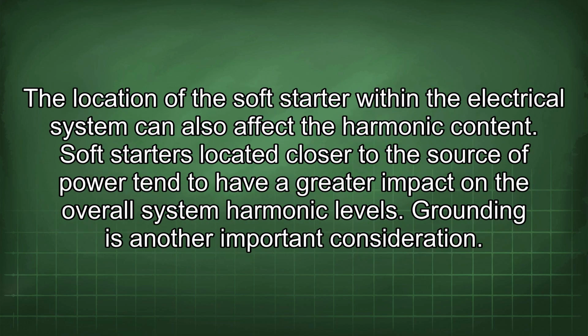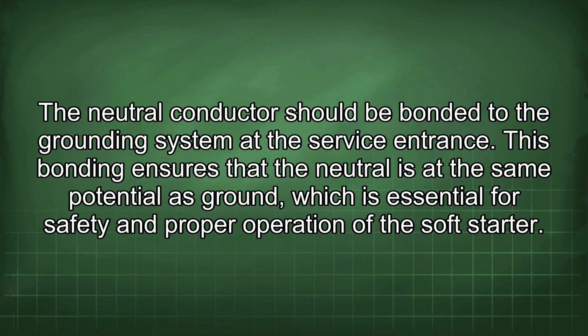System impedance plays a crucial role in determining the flow of harmonic currents. Low impedance systems allow harmonic currents to flow more freely, while high impedance systems tend to limit their flow. The location of the soft starter within the electrical system can also affect the harmonic content. Soft starters located closer to the source of power tend to have a greater impact on the overall system harmonic levels. Grounding is another important consideration. The neutral conductor should be bonded to the grounding system at the service entrance. This bonding ensures that the neutral is at the same potential as ground, which is essential for safety and proper operation of the soft starter.